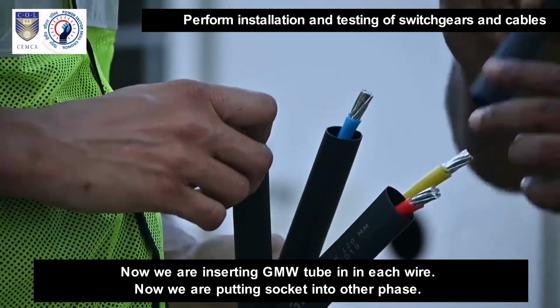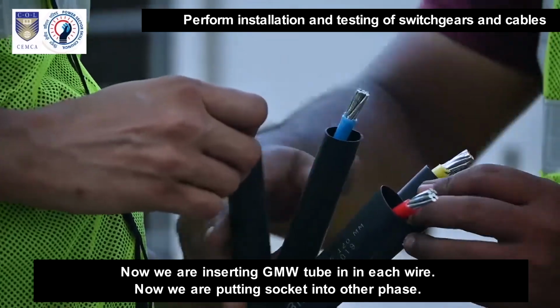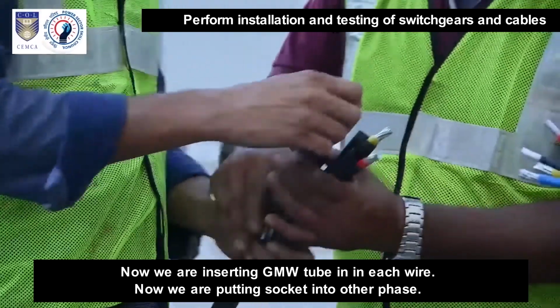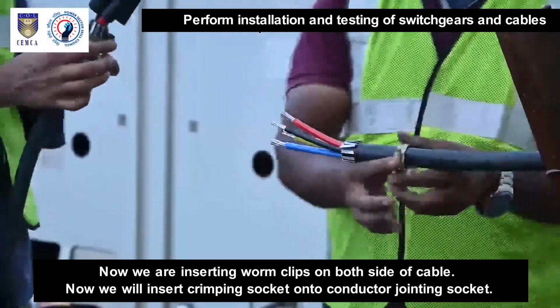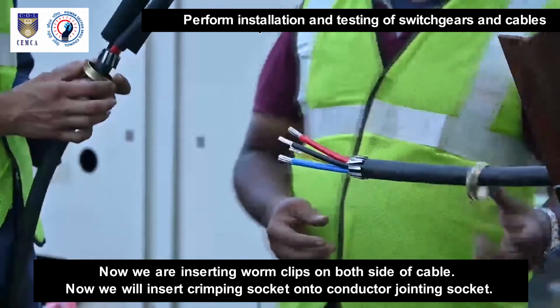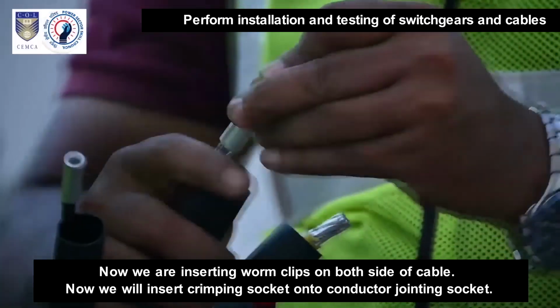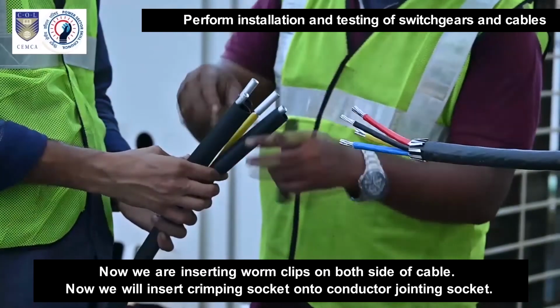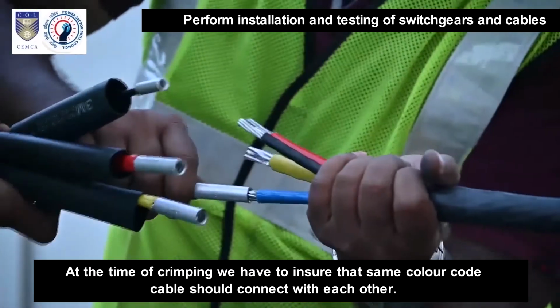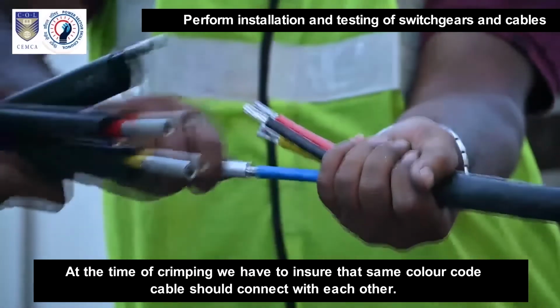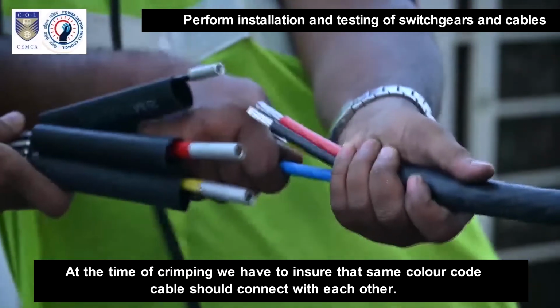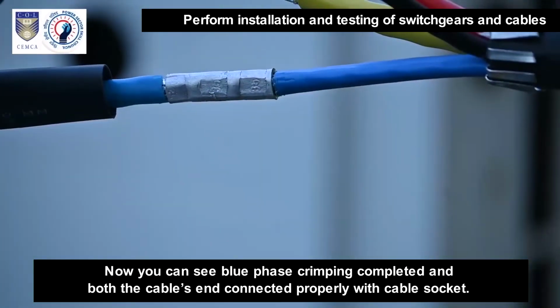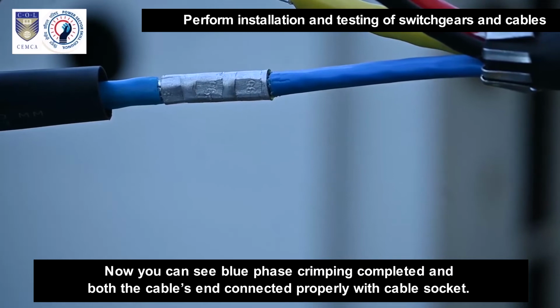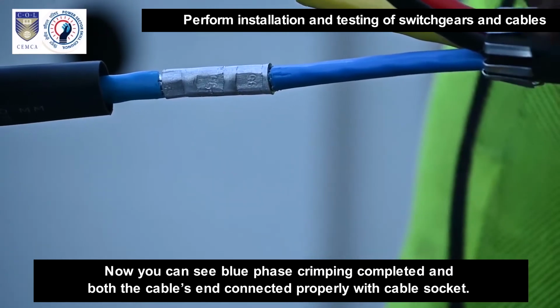Now we are inserting a GMW tube in each wire. Now we are putting the socket onto the other phase. Now we are inserting worm clips on both sides of the cable. Now we will insert the crimping socket onto the conductor jointing socket. At the time of crimping, we have to ensure that same color code cables are connected with each other. Now you can see blue phase crimping completed and both cable ends connected properly with the cable socket.